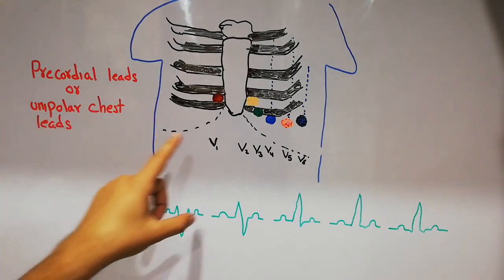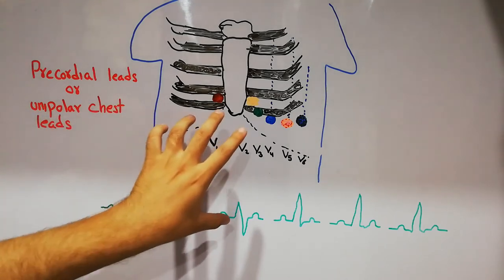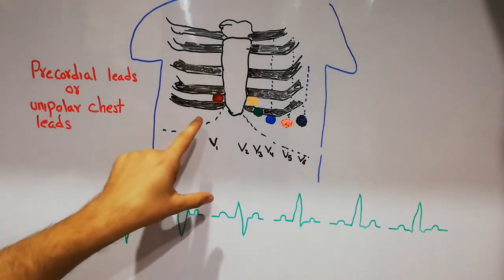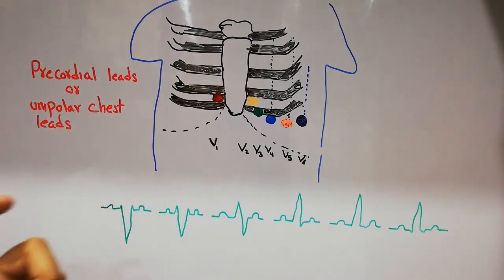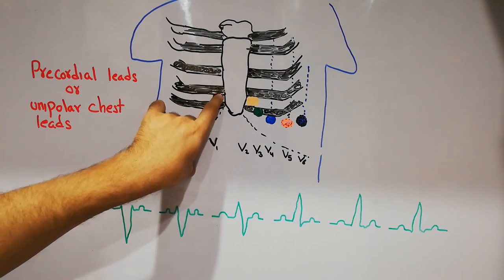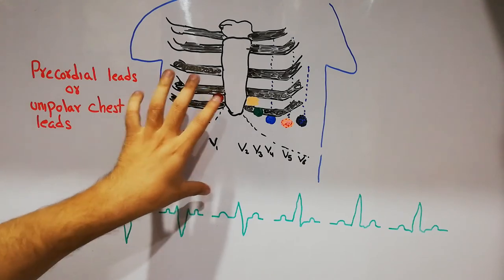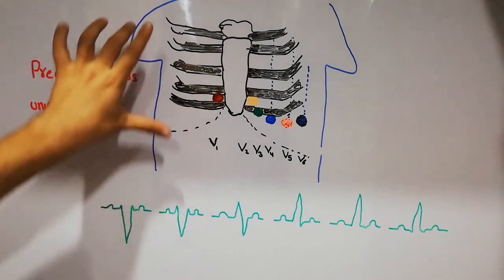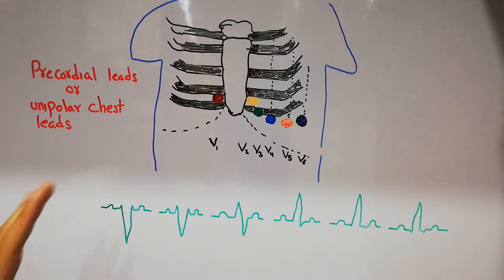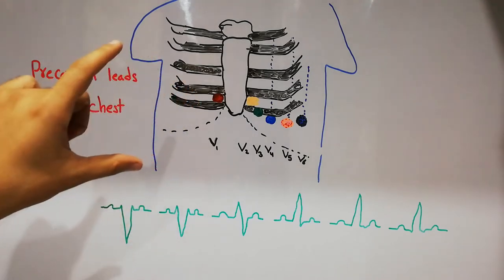The chest leads are 6 in number and they are placed in specific positions. They are unipolar because only one electrode is the active electrode, and that active electrode is placed on a specific area on the chest and is connected with 3 limb leads, which together behave as a neutral or indifferent lead, providing the reference so that the recording is made only from that specific lead.